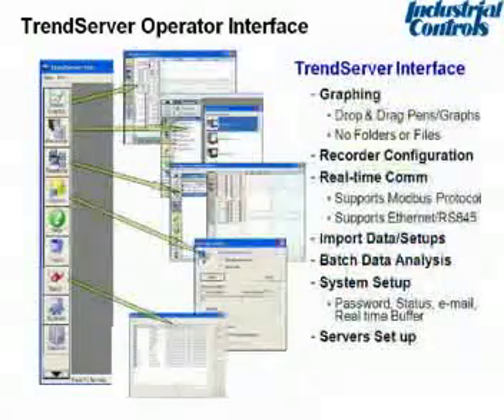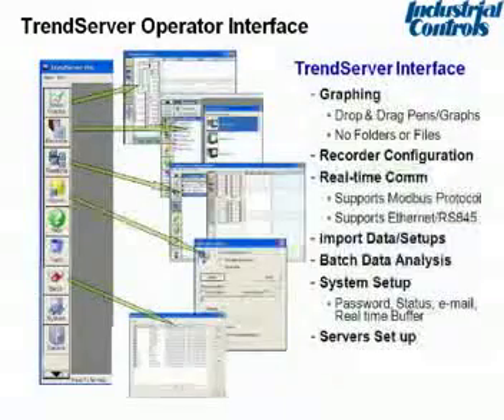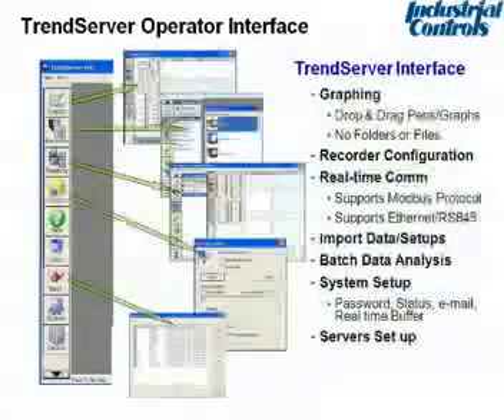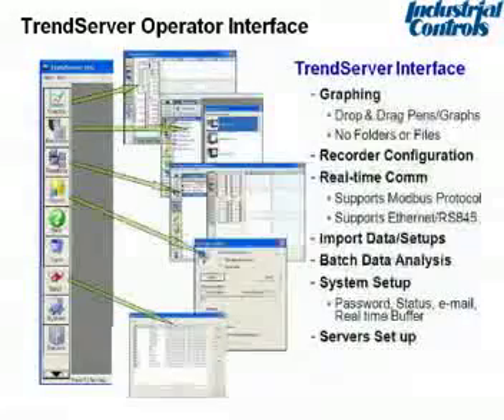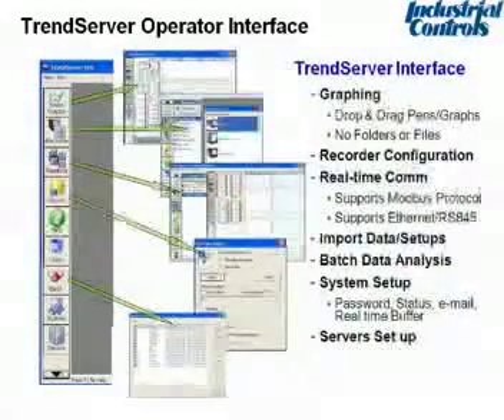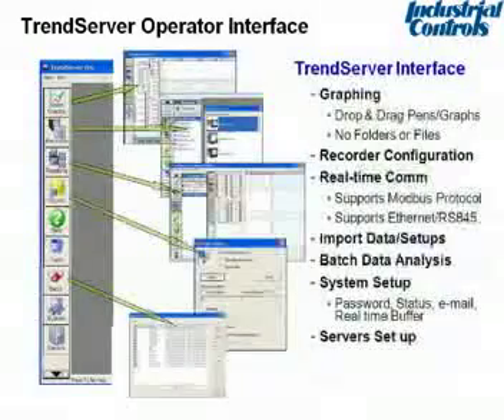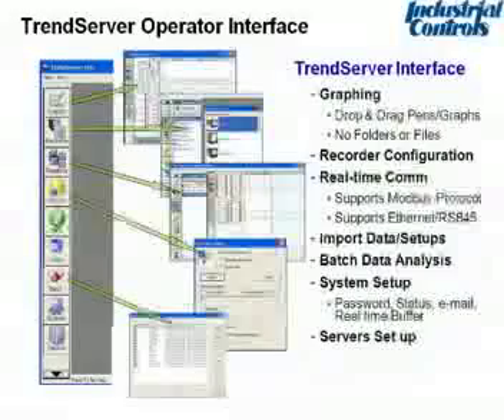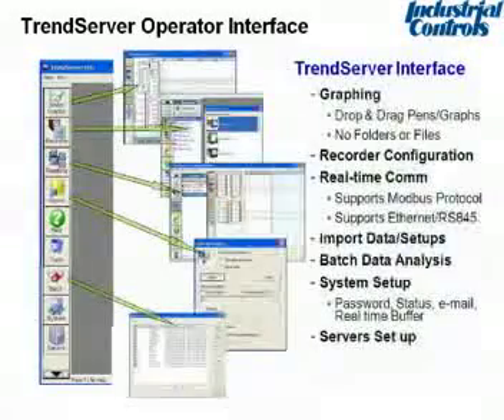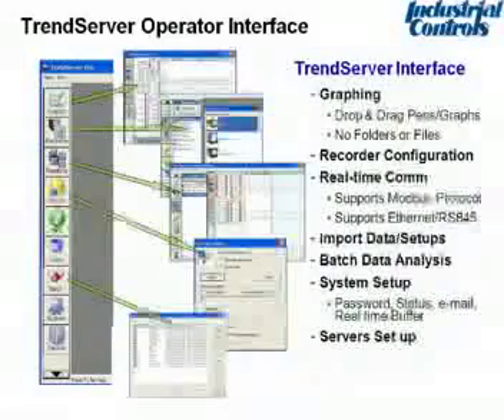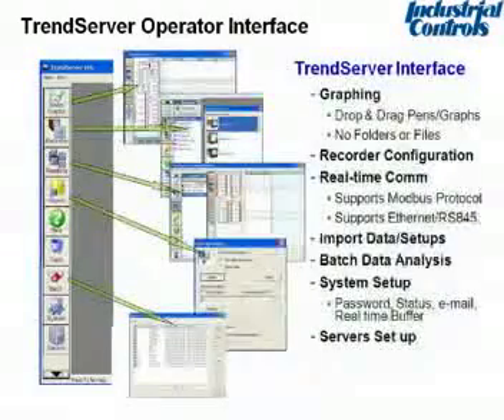So Trend Server Pro, that's the software I was referring to. It does a number of things. One, it's an offline configuration tool that allows you to do configuration. If you're not on the network, you can configure the recorder before it's delivered, download that to a jump drive, plug the recorder in when it gets delivered and powered up, upload that, and you're good to go, although you could actually configure the recorder at the touch screen.